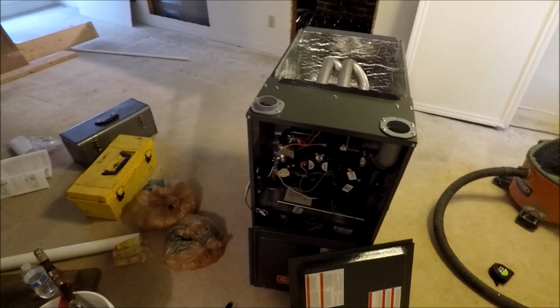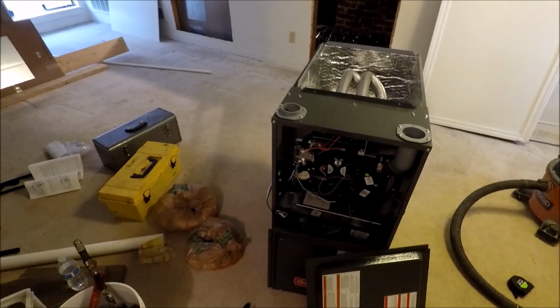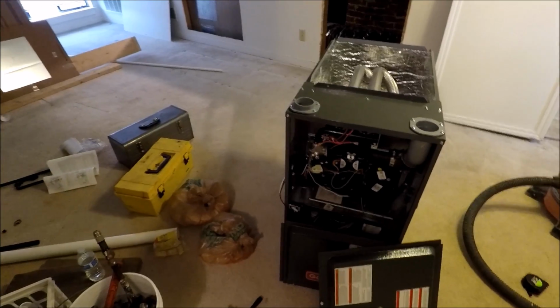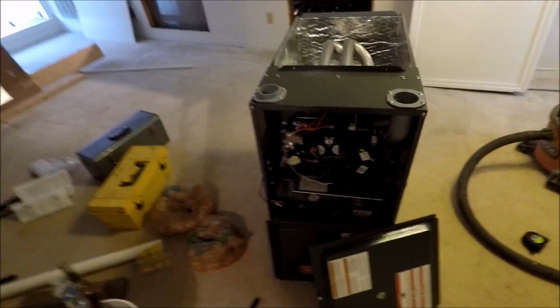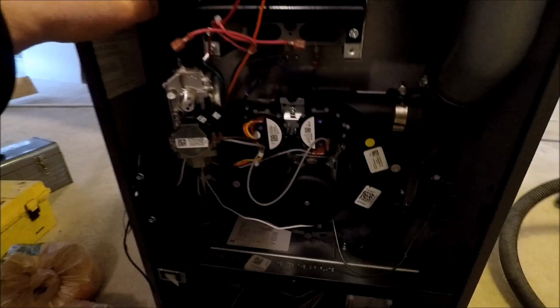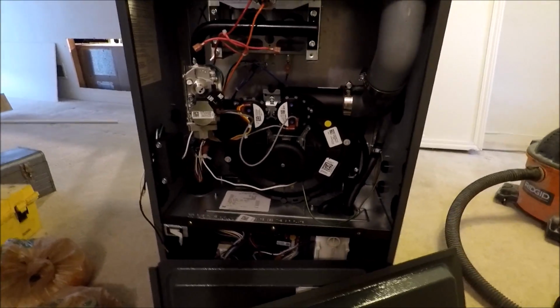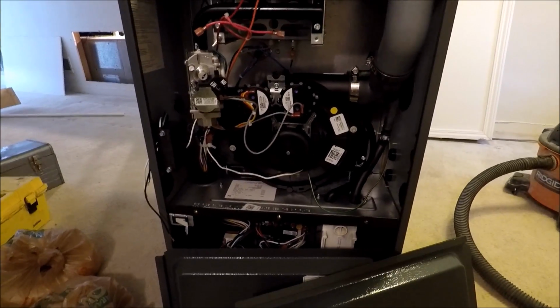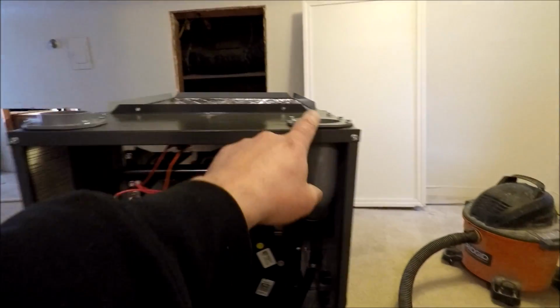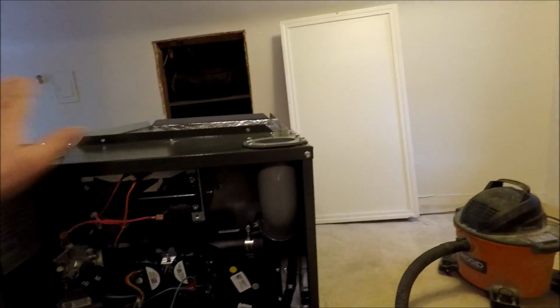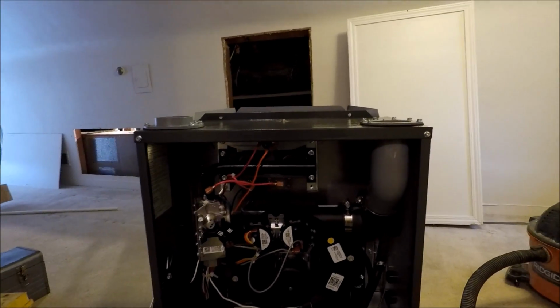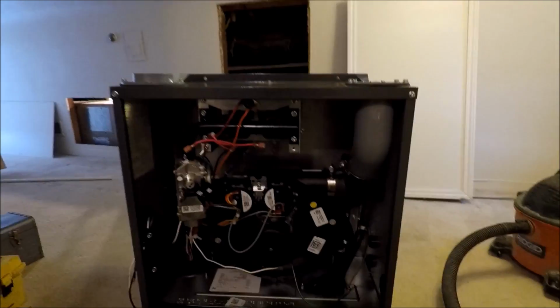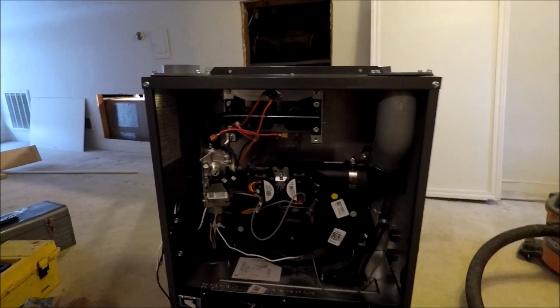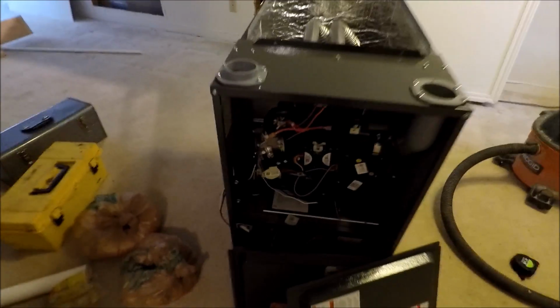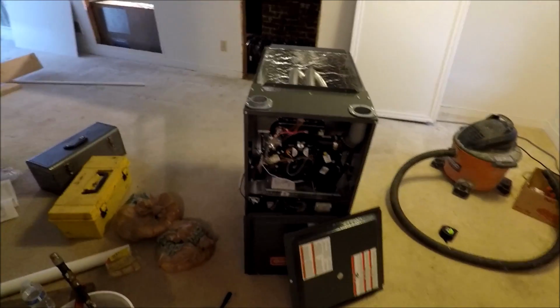If you have chemicals in there from the basement, dryer sheets, whatever it is, or if you're refinishing some woodwork in your basement, this will wipe out your secondary heat exchanger. That will corrode it up and you will have a problem with it. So even though you can use just the one vent, find a way to hook both of these up on every installation, and that will save your furnace from having major problems heat exchanger-wise, and having them go bad because they're corroding apart on you.